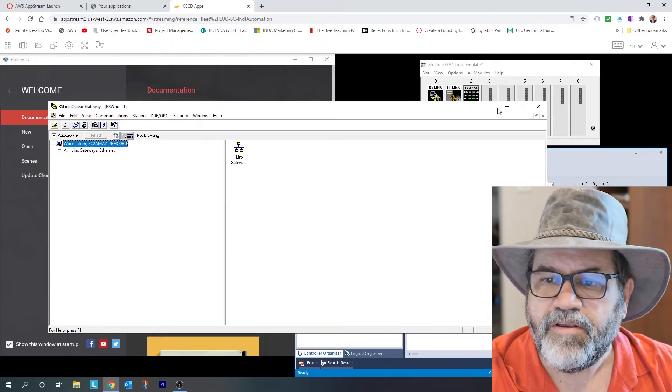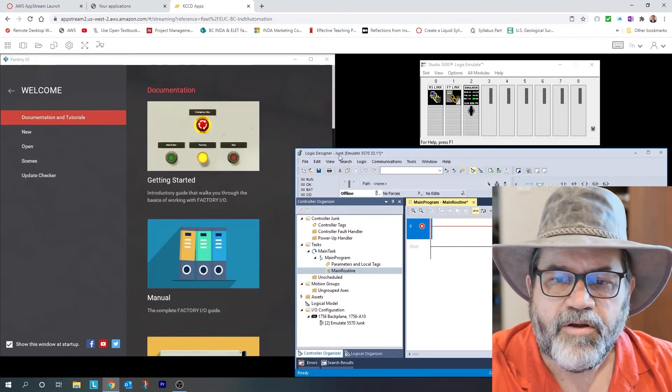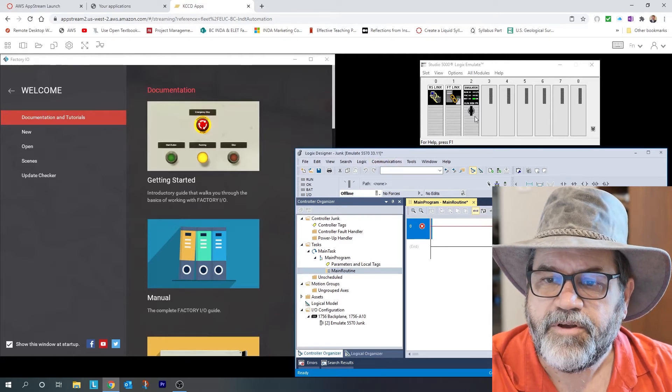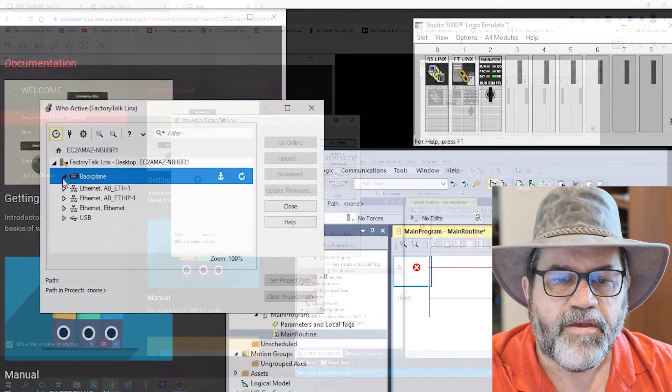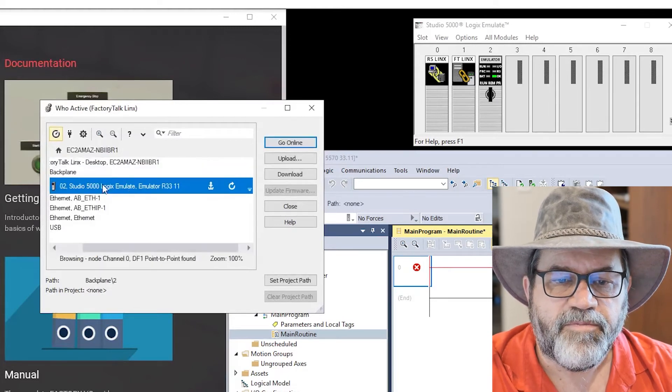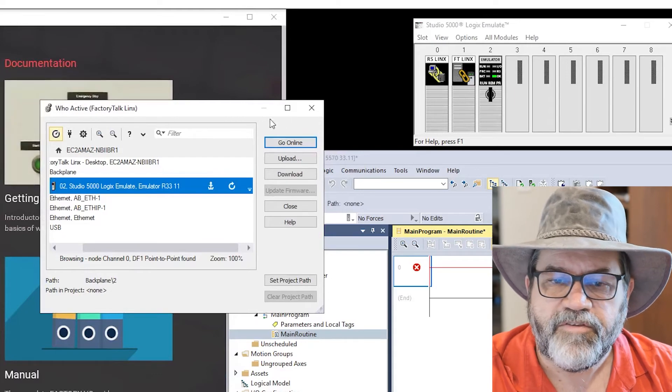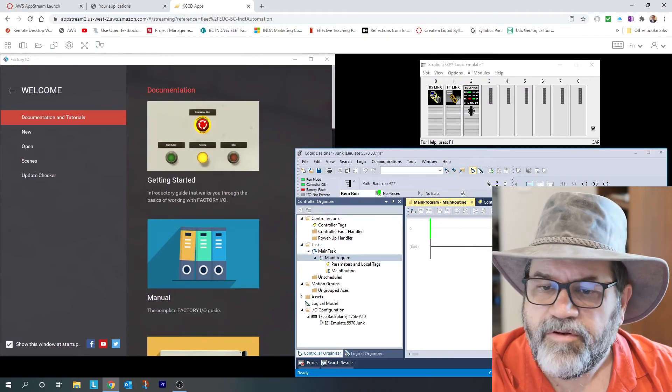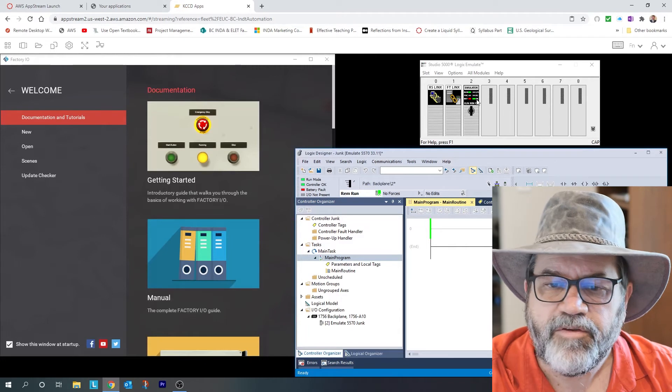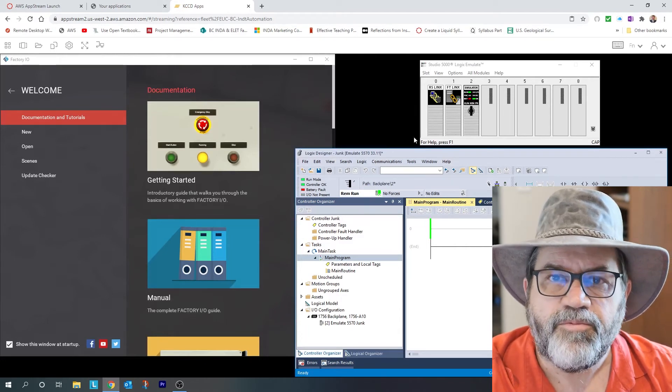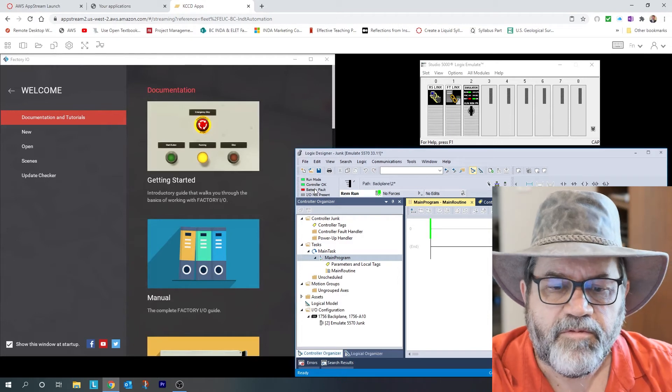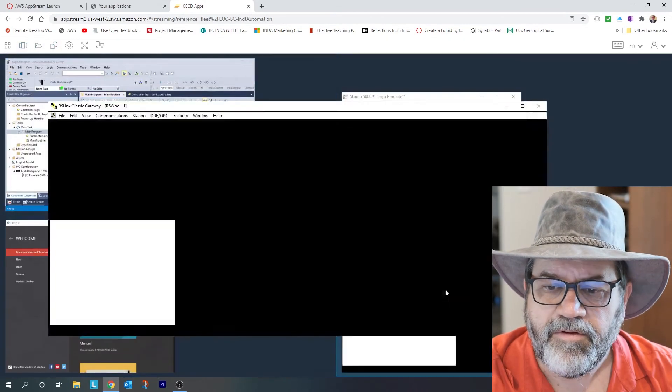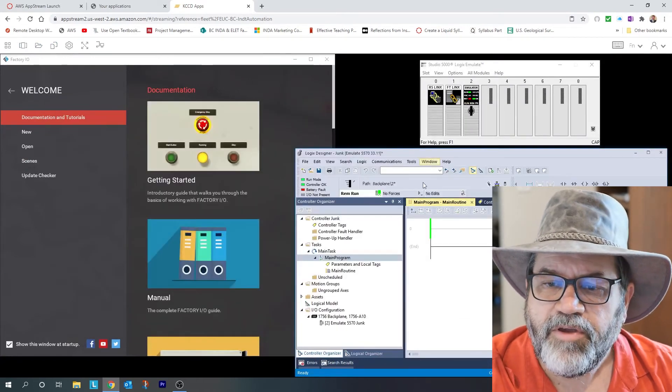Okay, so it's open and I'm going to minimize it because I don't have to do anything with it. I just have to have it running. All right. Now I want Studio 5000 to talk to my controller. That's that guy in slot two. So I'm going to go communication, who active and expand the backplane. And there in slot two is my controller. So this software has found this controller. And I'll go online. Okay, I've got green bars there. So that tells me that Studio 5000 is talking to this controller. Notice it's showing that I have a battery fault. And we don't need to worry about that. That's not going to stop us. If it was a problem, the RSLinx software that's running here in the background would go in and fix it for us. So we're going to ignore that for now.